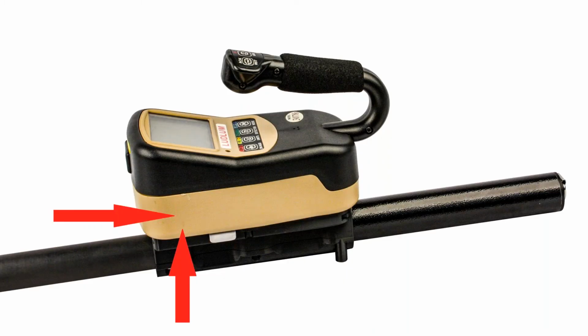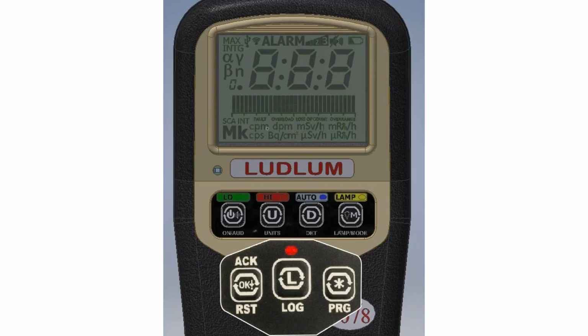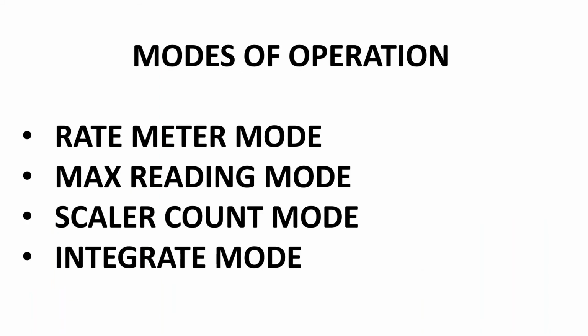The 3078i differs as it adds an internally mounted detector that's used to measure the dose to the operator. Both of these instruments have a large backlit LCD. It's digital and auto ranging and has 4 modes of operation: the rate meter mode, max reading mode, scaler count mode, and integrate mode. And calibration is done via the Ludlum calibration software.